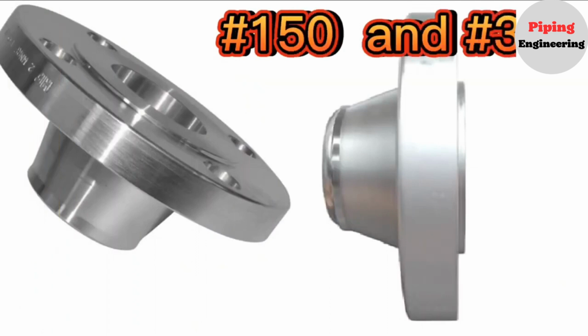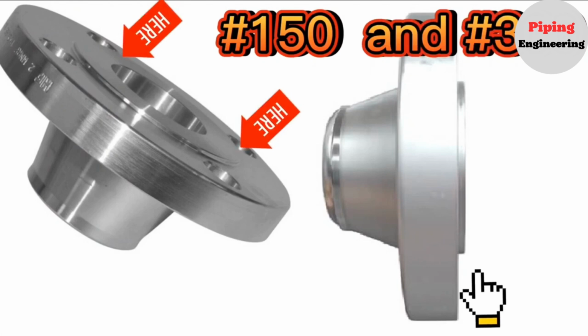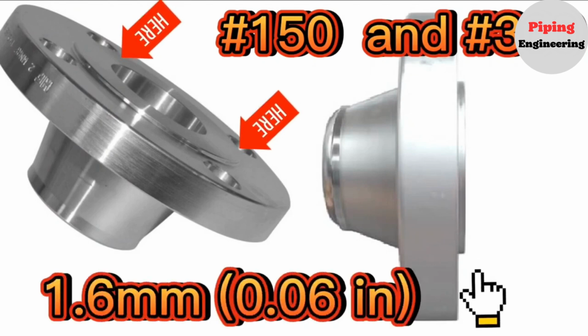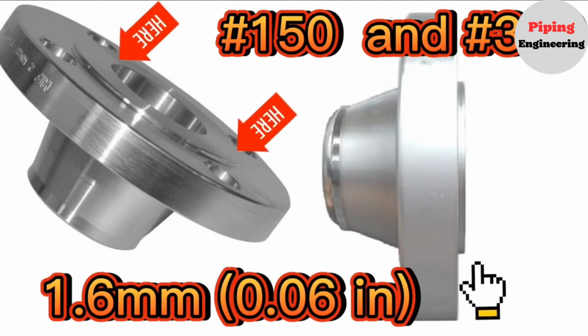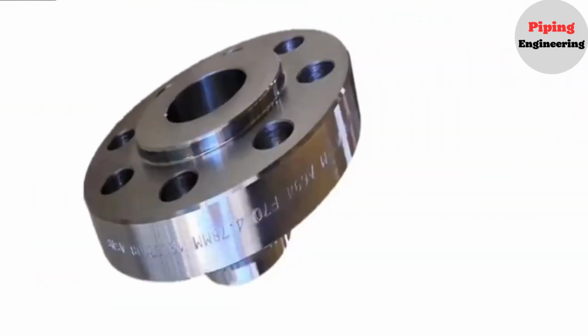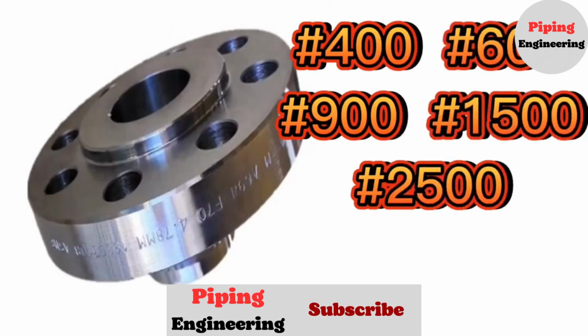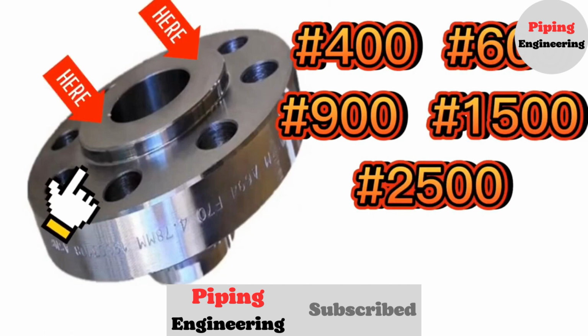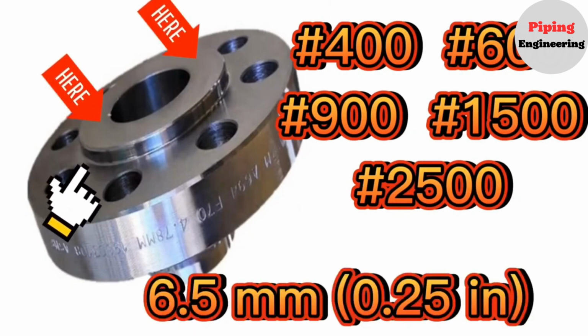Classes 150 and 300 pipe flanges and companion flanges of fittings are regularly furnished with a 1.6 mm (0.06 inches) raised seal face, which is in addition to the minimum flange thickness. Classes 400, 600, 900, 1500, and 2500 pipe flanges and companion flanges of fittings are regularly furnished with a 6.5 mm (0.25 inches) raised seal face, which is in addition to the minimum flange thickness.